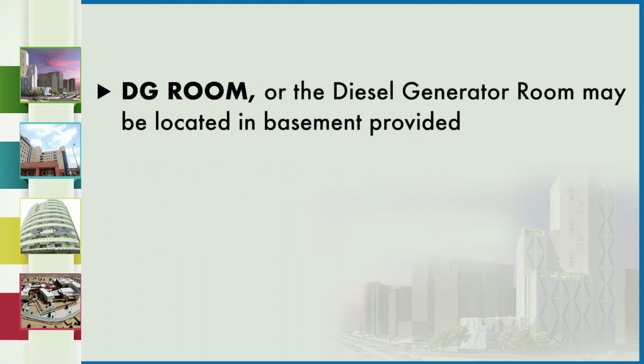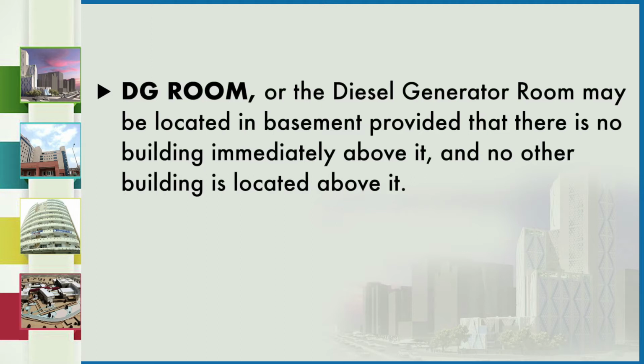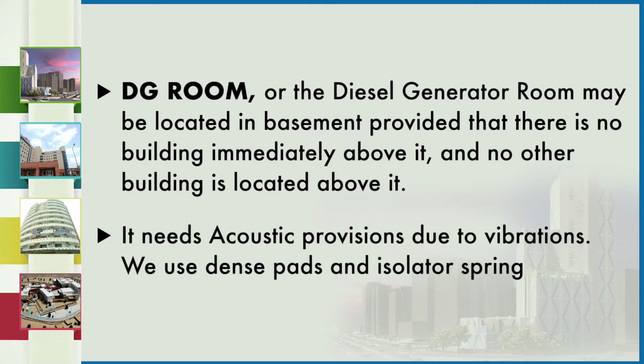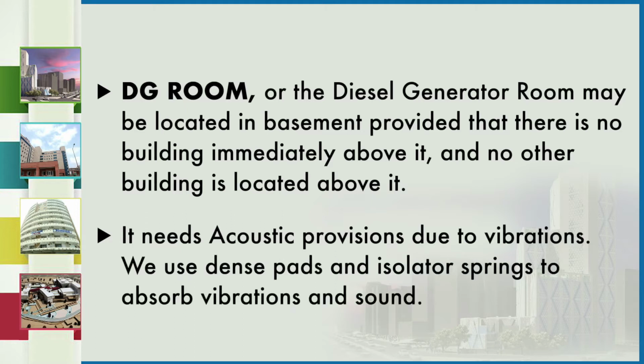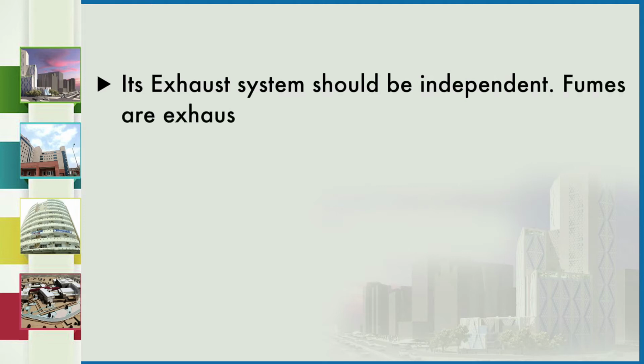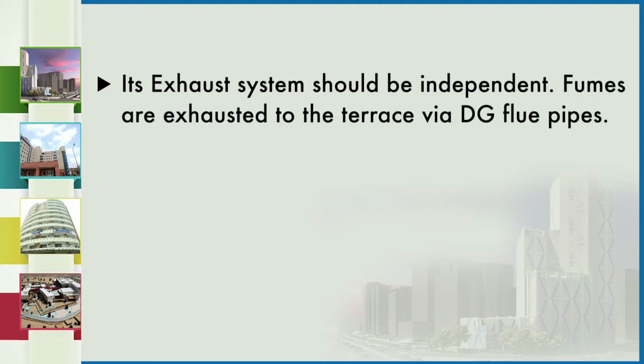The DG room, or the diesel generator room, may be located in the basement provided that there is no building immediately above it and no other building is located above it. It needs acoustic provisions due to vibrations. We use dense pads and isolator springs to absorb vibrations and sound. Its exhaust system should be independent. Fumes are exhausted to the terrace via DG flue pipes.